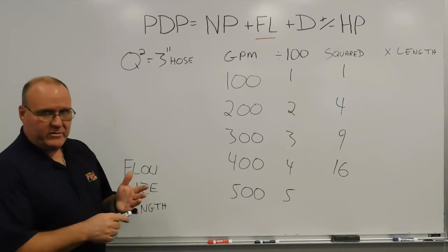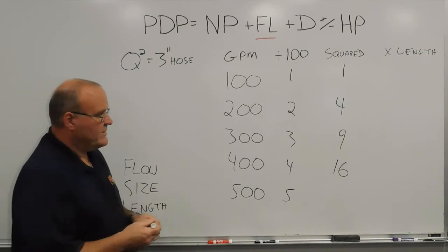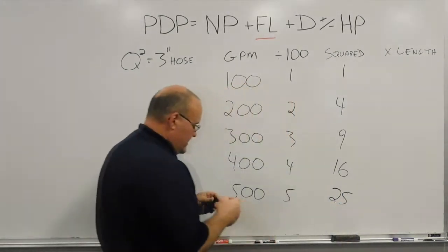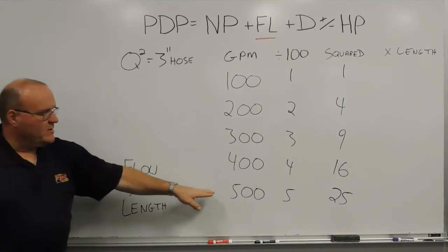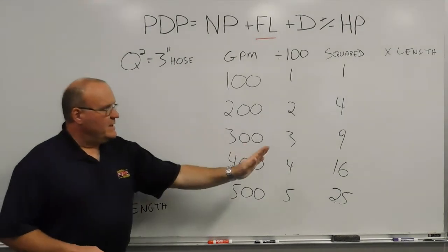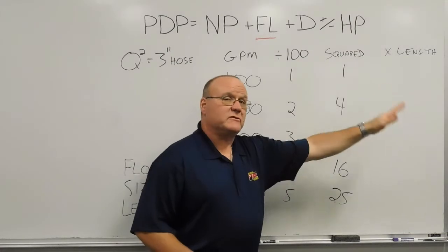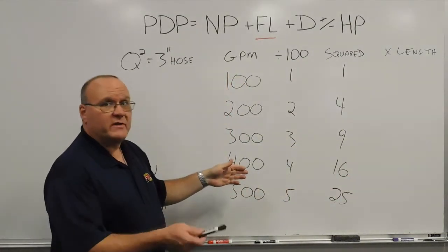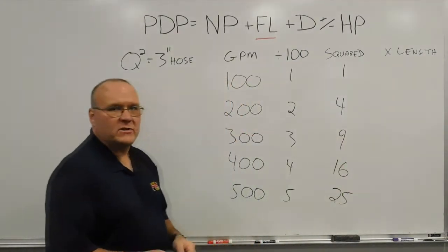And finally, 500 gallons a minute: 1, 2, 3, 4, 5 — knock off the zeros. 5 times 5 gives 25 pounds. At 100 feet of 3-inch hose flowing 500 gallons a minute, using the Q-squared method, there will be approximately 25 pounds of friction loss. From there, take this number and however many feet of hose there is, knock the zeros off that too — 500 feet of hose would be 5 — then multiply to get your total friction loss based on length.